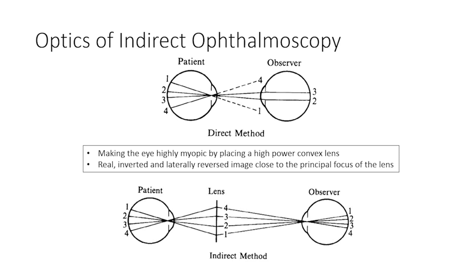There is a whole chapter on optics of ophthalmoscopy in most textbooks, and I would like to refer to the fine chapter in Duane's ophthalmology for further reading. However, I would like to stress on two important aspects of optics related to indirect ophthalmoscopy. The first and most striking feature is the use of a high power convex condensing lens which makes the eye highly myopic, resulting in a real, inverted, and laterally reversed image close to the principal focus of the lens.